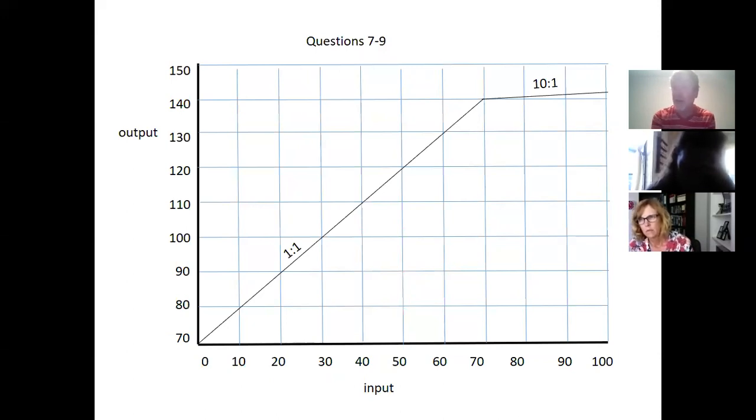It's like slamming on the brakes. The output barely increases at all. There's a little bit of a tilt to the line, so there's a little bit of give, but basically this is a hearing aid where compression is slamming on the brakes. So this is basically so that they don't have distortion, or to help the distortion. Correct. It limits the MPO without distortion. Correct. That's the idea of it. Fighting cavities was the whole idea behind Crest, and limiting the maximum power output is the whole idea behind output limiting compression. We're good. This is good.